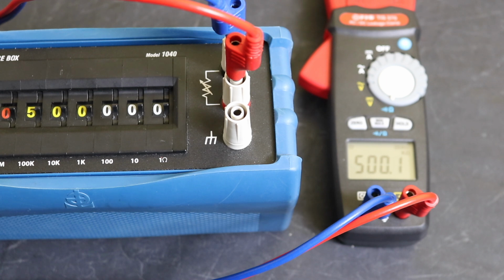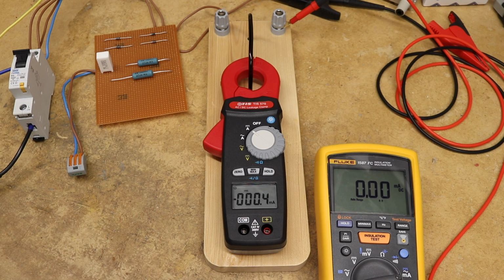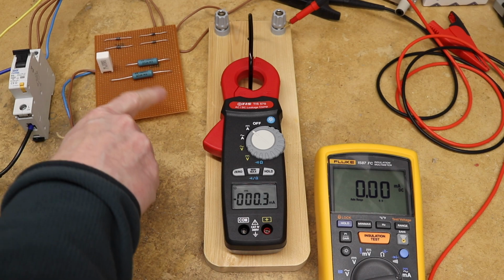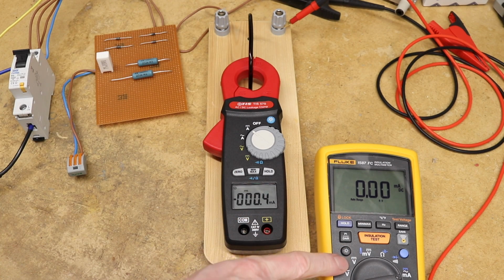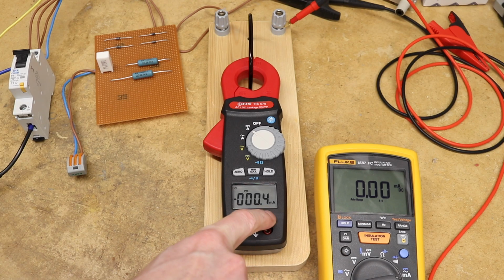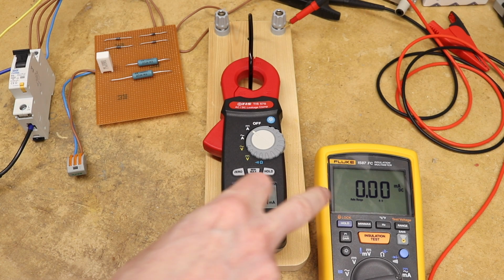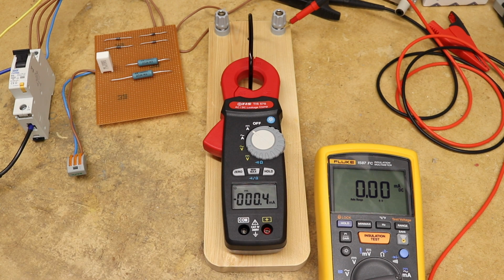What I want to do is set this all up on an AC circuit with some DC milliamps injected and just see if that affects the accuracy of the current clamp. So what I've set up here is a little mad experiment to measure the DC actually on an AC circuit. I have a little board here to rectify and put some DC power in through my loop. I've got my Fluke 1587FC, which is in series with our TIS570, so the readings on these should actually match. We have our RCD here, and just out of picture I've got a little transformer, you'll hear that buzz, just to provide me with some AC load as well.